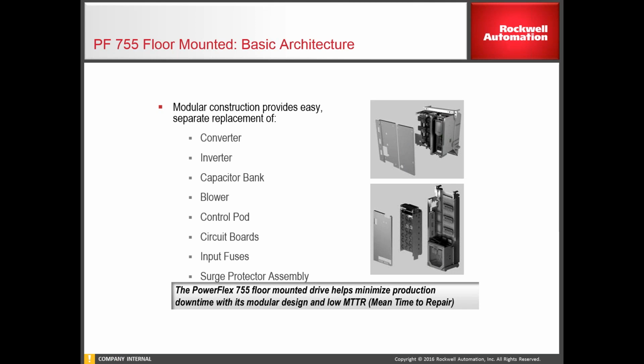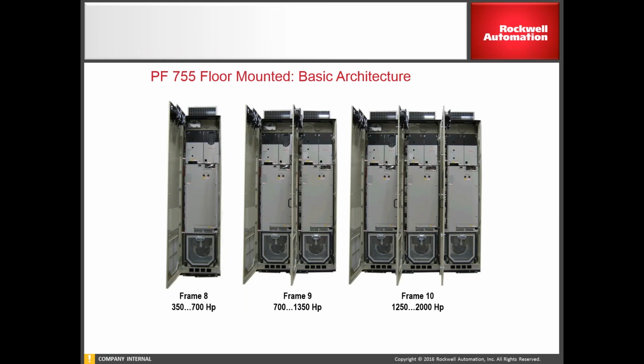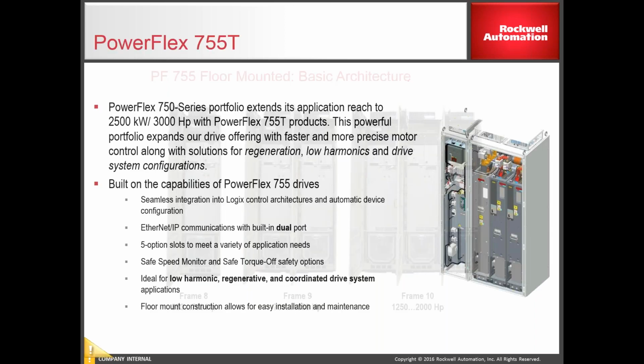And that drive is a modular drive. So you've got control pods, you've got your converter section, your inverter section, you've got a cap bank. So if you have to replace something, you don't have to roll out the entire cart. You can take out the module that you need to have replaced, and it just makes it easier to troubleshoot that way. So again, that would be your frames 8, 9, and 10 with the 755.